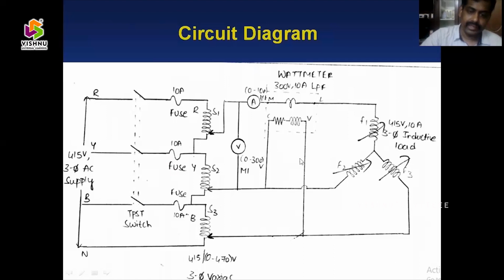Why? Because we could apply the rated voltage. What is the rated voltage here? 415 volts. If you apply the rated voltage to this load, you will get more magnetic hum. I mean, we will get more magnetic noise. That is the reason why we are supplying only 120 volts, right? Once you supply 120 volts, then we can start.